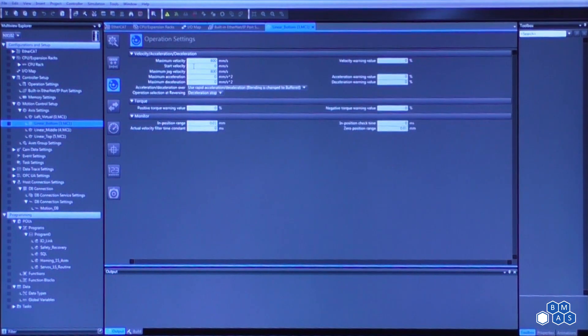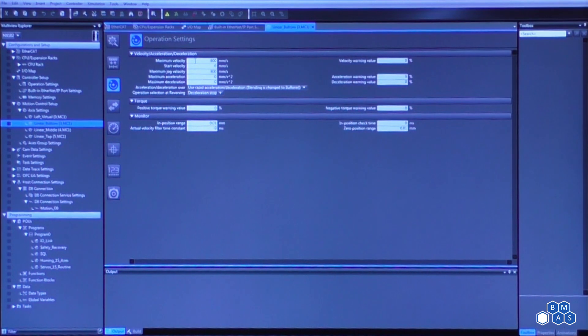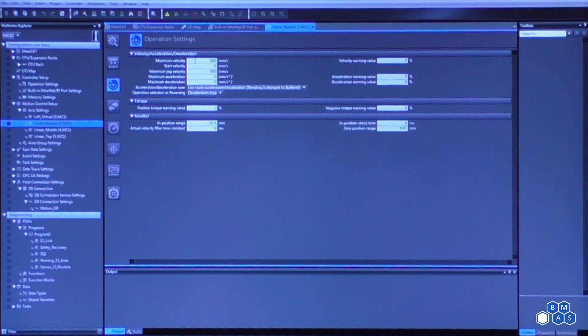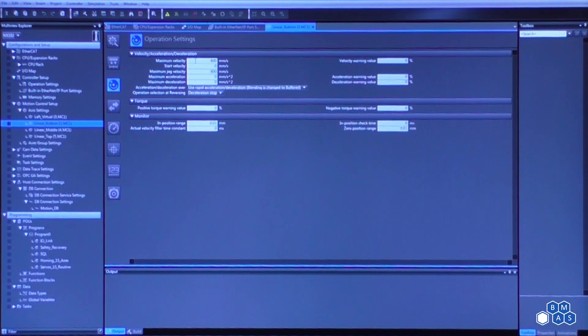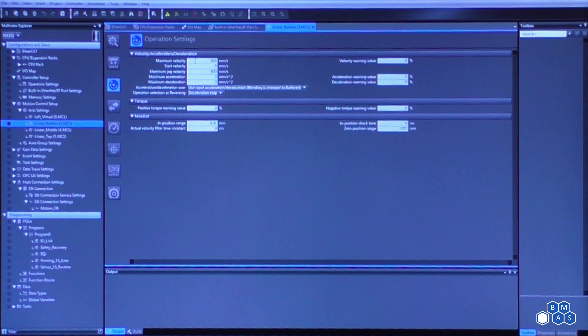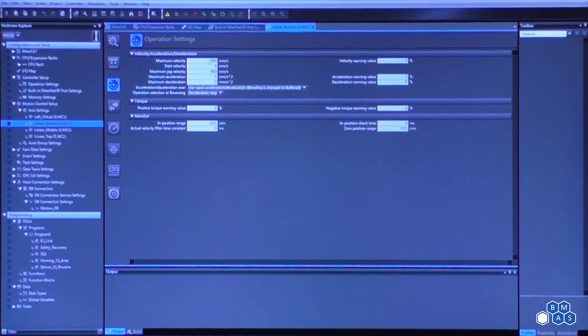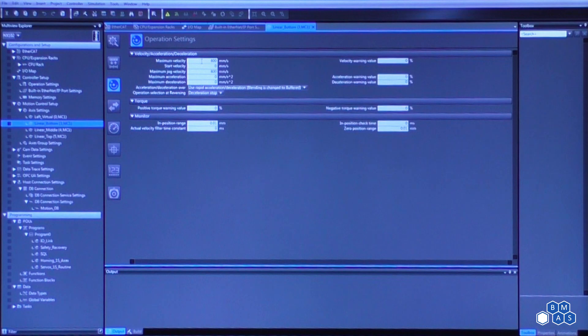Once we apply this, we can now go in and identify some of the other configuration settings. I'll just point out those that are the most common. The maximum velocity, this is what never to exceed. So as we're setting up our axis, we can either make this maximum velocity something that's system dependent or motor dependent. What I mean by that is the motors are going to be rated up to a maximum or a continuous maximum speed, and we want to set this to a maximum velocity at that maximum continuous speed rating or the mechanics of the system. We simply don't want this system to exceed a maximum velocity. This is where we would apply that. The maximum jog velocity is also something that we would need to set that would need to be the same or lower than the maximum velocity.